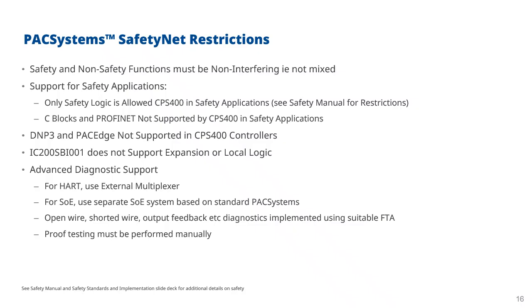And if there's any sort of proof testing, that must be performed manually. So typically that would involve some sort of push button, or possibly being done by the HMI SCADA, but bearing in mind what I said before about writing to the PLC, and that would be a manual test that's performed. Currently, we're also not implementing pulse tests, so that's another reason where proof testing comes in. That capability to do pulse testing to resolve issues is not currently supported in our existing VersaMax IO modules.